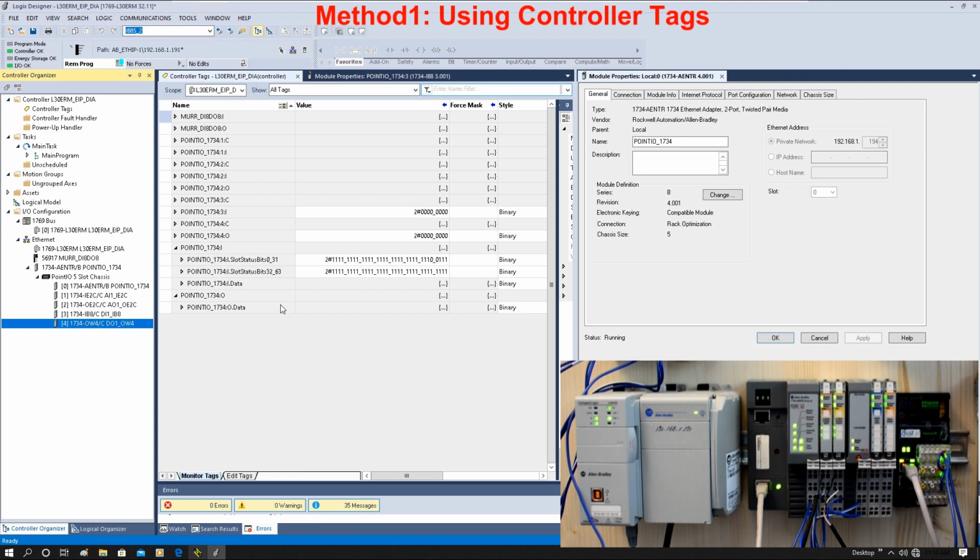So for example, this is the power module, and after this power module, at the right side, this is the input and output module. If I disconnect the power, so now this module lost the power. We can see, because this station cannot find this device here, this module, it also shows 1. Okay, so now I return the power.